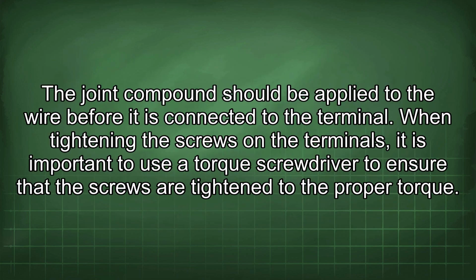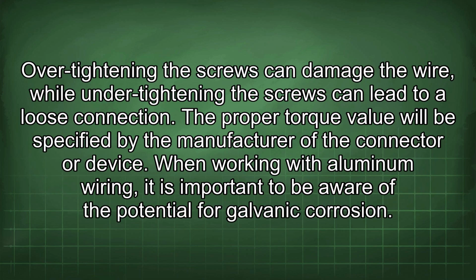The joint compound should be applied to the wire before it is connected to the terminal. When tightening the screws on the terminals, it is important to use a torque screwdriver to ensure that the screws are tightened to the proper torque. Over-tightening the screws can damage the wire, while under-tightening the screws can lead to a loose connection. The proper torque value will be specified by the manufacturer of the connector or device.